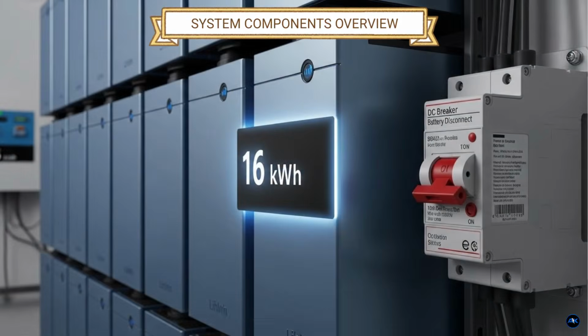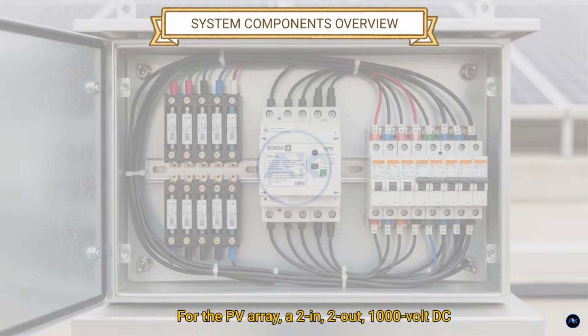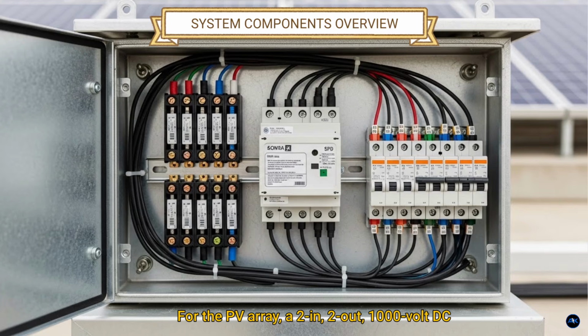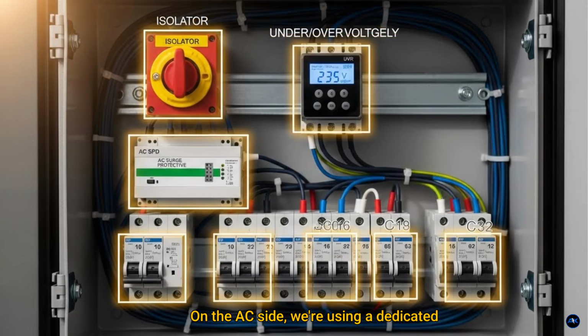Energy storage is handled by a 16 kilowatt-hour lithium battery pack, providing reliable backup capacity and long cycle life. A dedicated DC battery breaker is included for protection and service isolation. For the PV array, a 2-in, 2-out, 1000-volt DC combiner box consolidates panel strings and adds an extra layer of safety with integrated protection devices. On the AC side, we're using a dedicated distribution box equipped with an AC isolator, an under-over voltage protection relay, surge protection, and circuit breakers to ensure stable and safe operation.